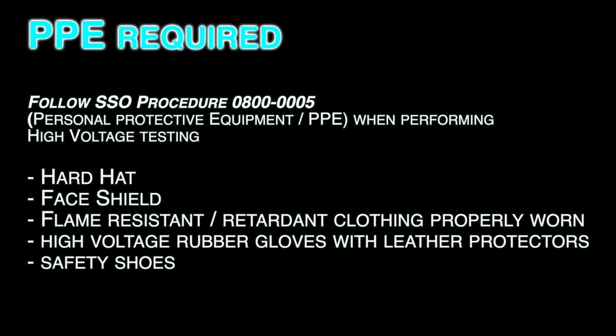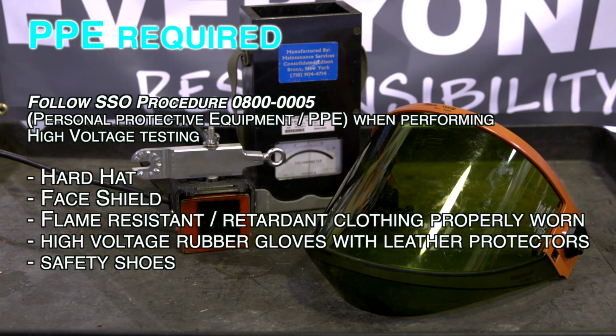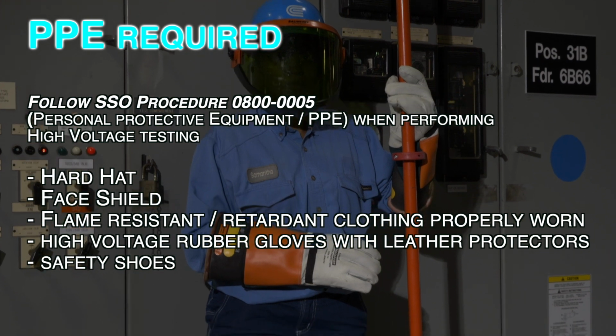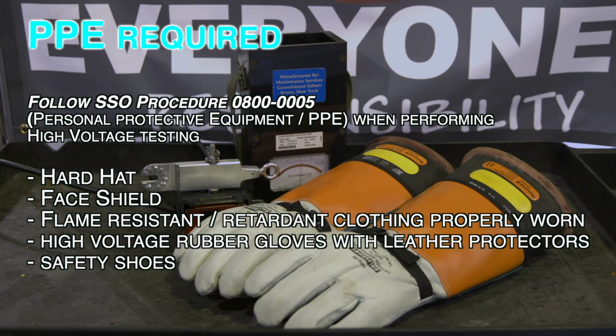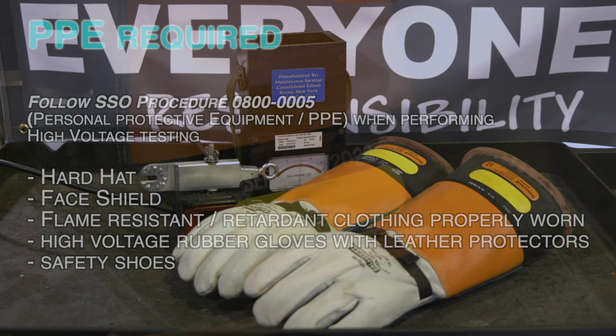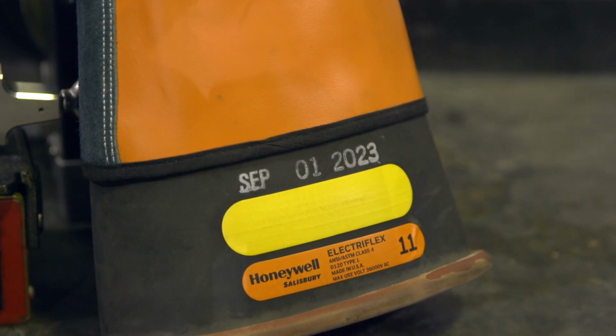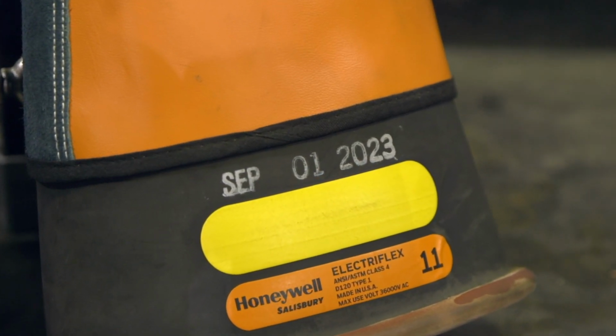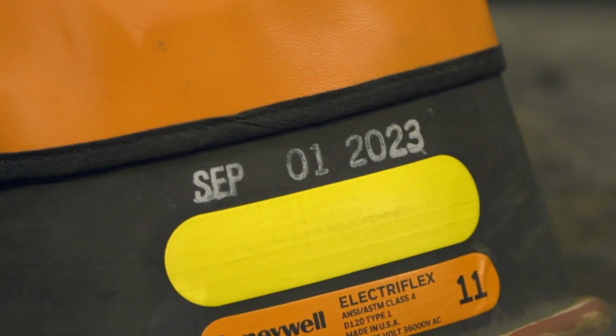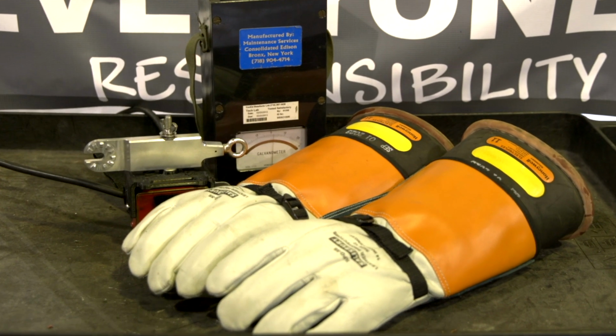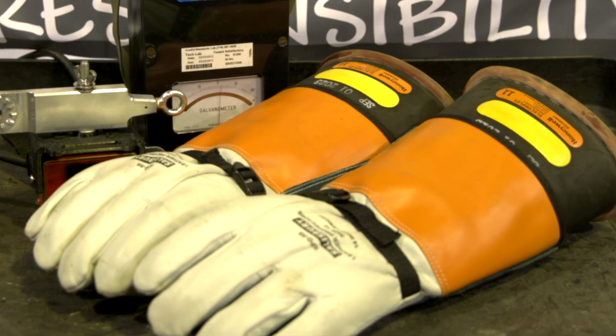The PPE required for this job function, as per procedure 800-0005, personal protective equipment, when performing high voltage testing, are as follows: hard hat, face shield, flame resistant or retardant clothing worn properly, high voltage rubber gloves with leather protectors, and safety shoes. Prior to wearing your rubber gloves, please check the expiration date. If the gloves are expired, don't use them. Request a new pair. Don't forget to check your leather protectors as well for any visible damage.